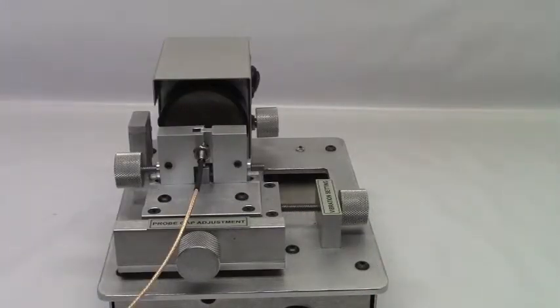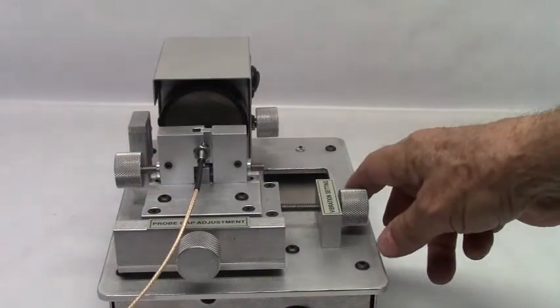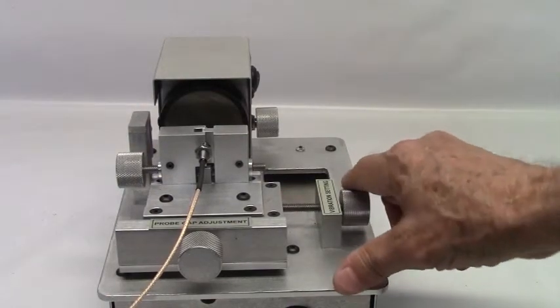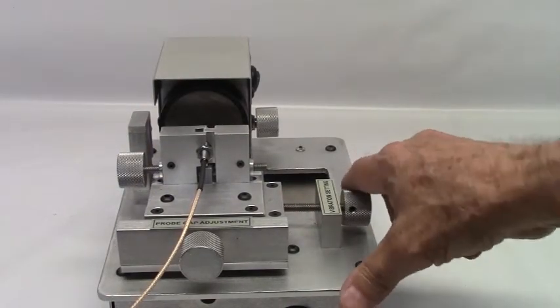Five, a wobble plate that will let you simulate any degree of vibration from 1 to 40 mils, with a fine-tuning means that lets you move the probe along the front of the wobble plate with no play in the bearings. This is the vibration setting knob that you turn this way to move in this direction.